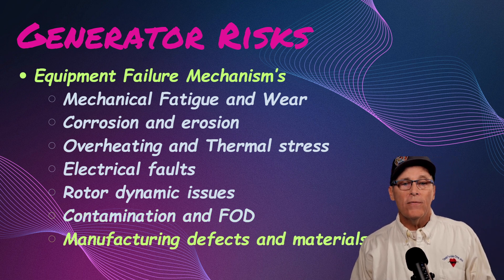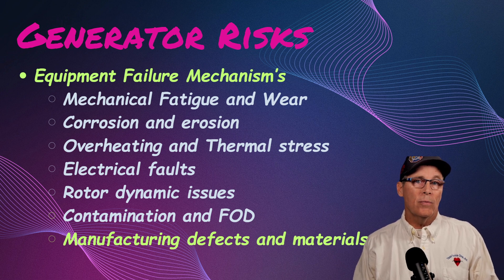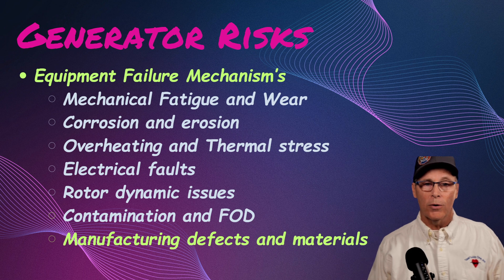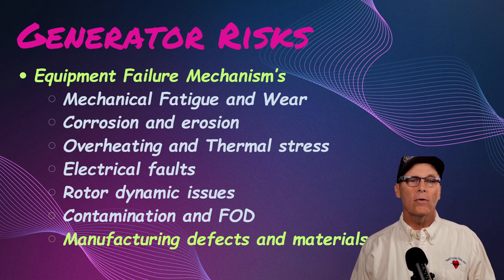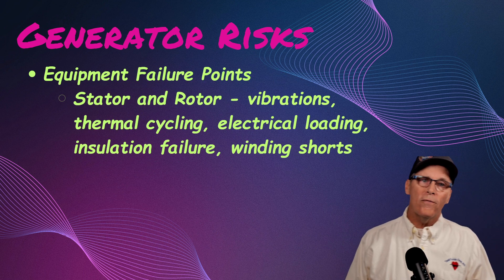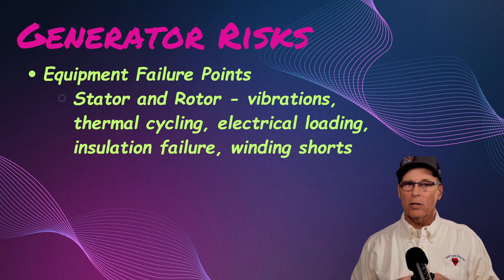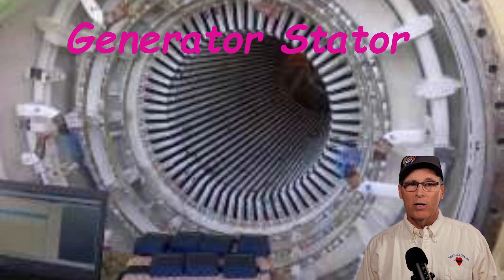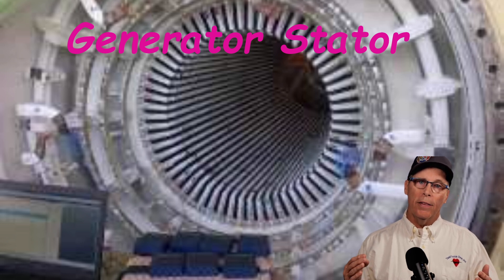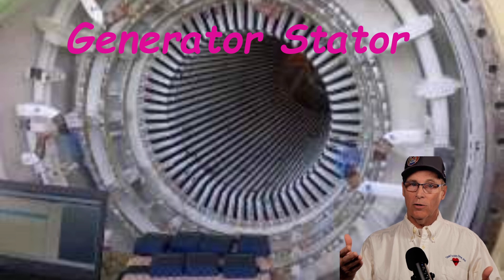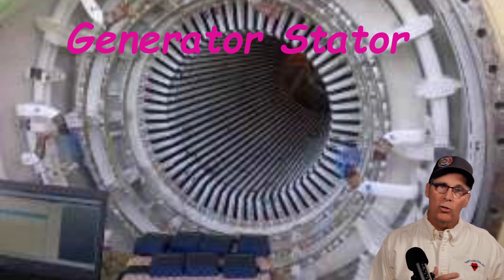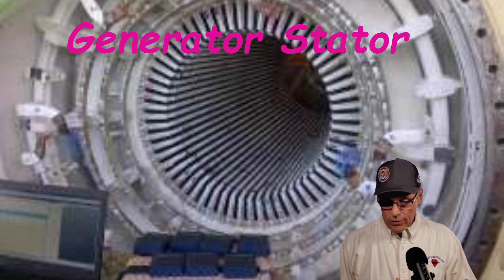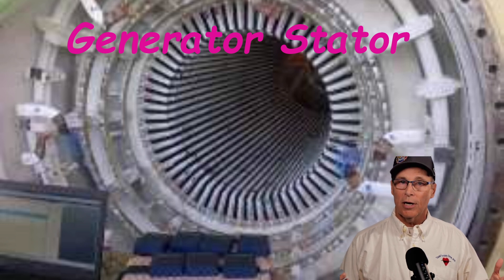Overheating occurs when you're not cooling the material properly. Manufacturing defects in the materials are another concern — these machines are assembled in a factory, shipped across the world, and installed. Defects and material problems are typically discovered early in the life of the machine. Failures occur in the stator and rotor — vibrations, electrical loading, insulation failure, and winding shorts. Stators can be hydrogen-cooled or air-cooled. Hydrogen-cooled units have hollow bars with hydrogen flowing through them, introducing a fire hazard. Hydrogen seal oil keeps the hydrogen contained — if the seal oil system is not working, hydrogen can leak out.